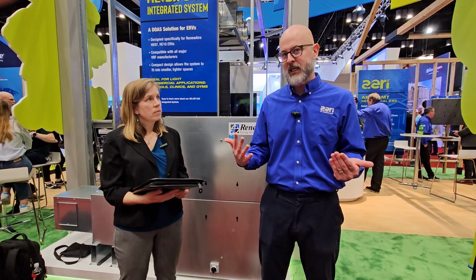Yeah, so really you have two options. You can duct the unit, like have its own separate duct. The problem there is an ERV isn't meant to fully condition the air. It's to remove the initial bit of load, right? So let's say 0 degrees outside, 70 inside, we're going to warm the air up to about 50. However, that sounds great and is amazing, but in the winter, you don't want to dump 50-degree air on people's heads, right? And that's why you typically are integrating into a larger system.